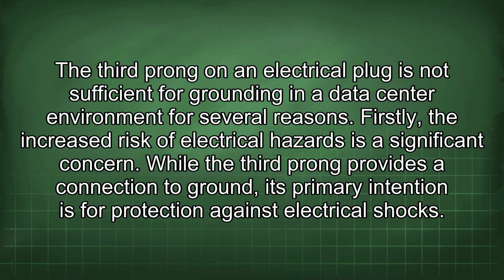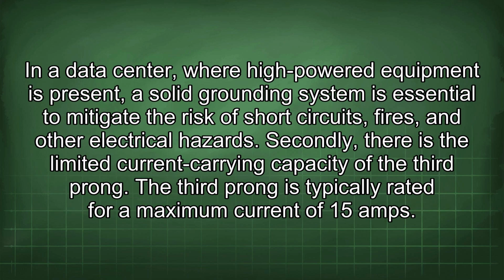The third prong on an electrical plug is not sufficient for grounding in a data center environment for several reasons. Firstly, the increased risk of electrical hazards is a significant concern. While the third prong provides a connection to ground, its primary intention is for protection against electrical shocks. In a data center, where high-powered equipment is present, a solid grounding system is essential to mitigate the risk of short circuits, fires, and other electrical hazards.